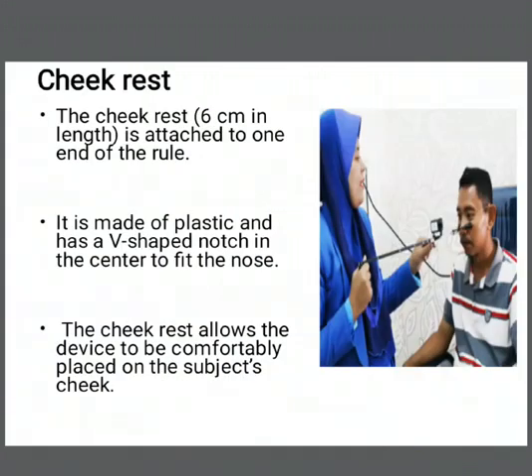The cheek rest is six centimeters long and is attached to one end of the square rule. It is made of plastic and has a V-shaped notch in the center to fit the nose of the patient. The cheek rest also allows the device to be comfortably placed on the patient's cheek.